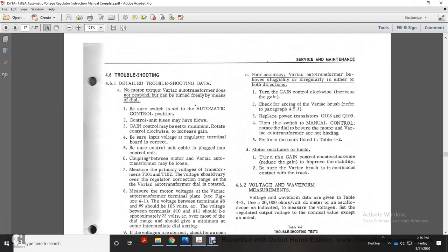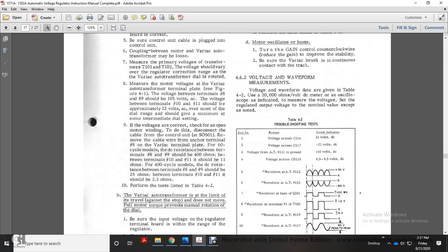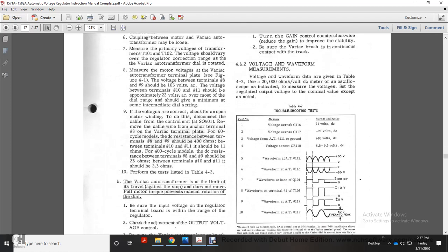C. Poor accuracy, Variac autotransformer, sluggish irregularity, either or both directions. Turn gain control clockwise, increase the gain, check for arcing of the Variac brush, refer to paragraph 4.5.1. Turn switch, manual control to rotate dial to be sure of the motor and Variac autotransformer is not binding. And 5. Perform the test listed in table 4-2. D. Motor oscillates or hunts. Turn the gain control counterclockwise, reduce the gain, improve its stability, make sure variadic brushes are continuous contact with the track. Alright, 4.6.2 show the voltage waveform measurements.